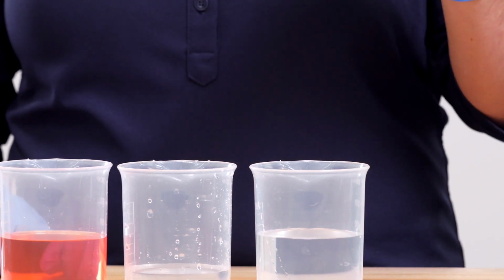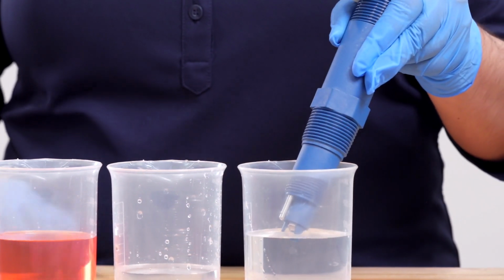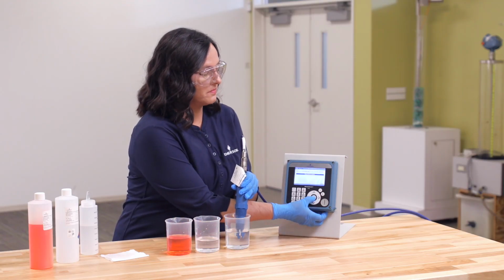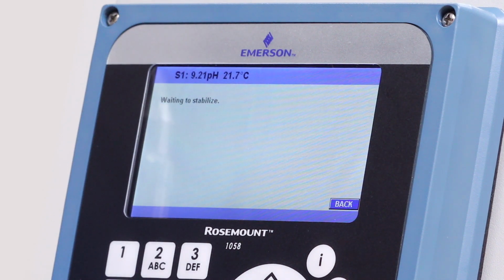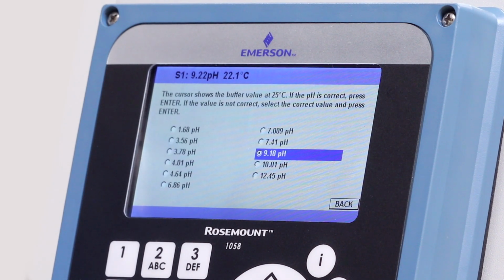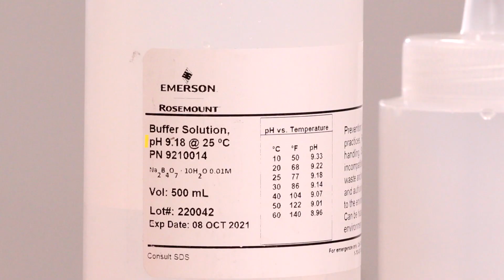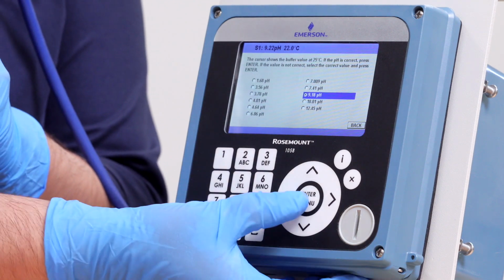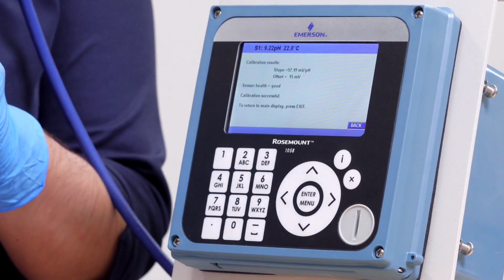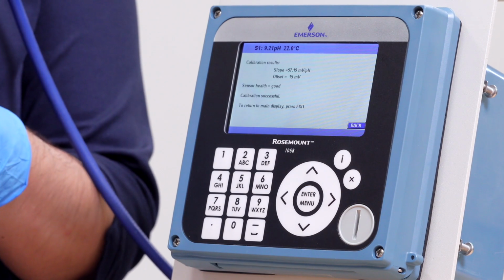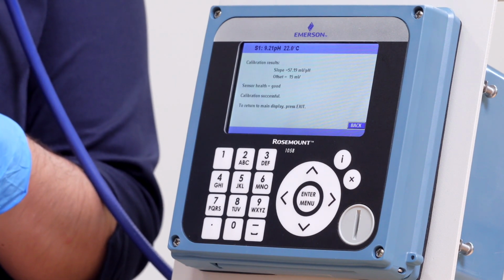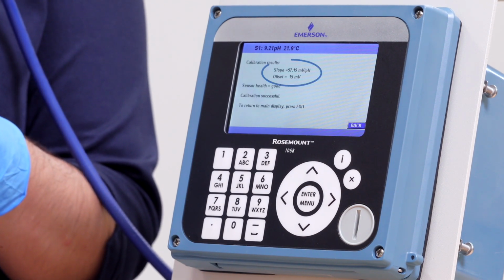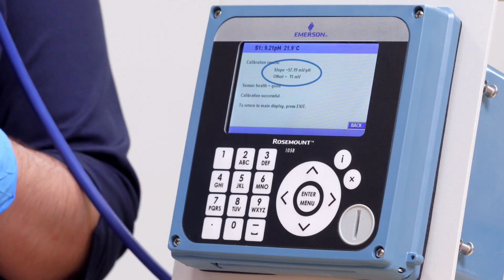Place the sensor in the second buffer and press Enter. Wait for the readings to stabilize. Then select the solution that matches the value shown on the bottle and press Enter. After this calibration sequence is complete, the transmitter will display a slope and offset.